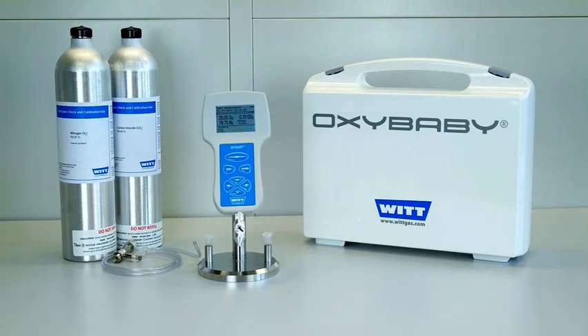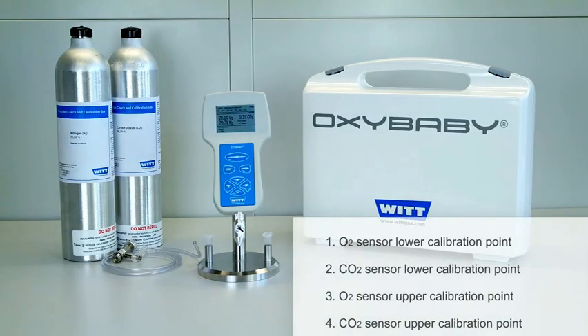Your Oxybaby has to be calibrated at regular intervals. For the majority of applications, a weekly calibration is sufficient. The calibration of the Oxybaby for oxygen and CO2 takes place in 4 steps. First, you'll calibrate the lower calibration point of the oxygen and then the CO2 sensor. In general, these are the 0 points. The next step is to calibrate the upper calibration points of the 2 sensors.